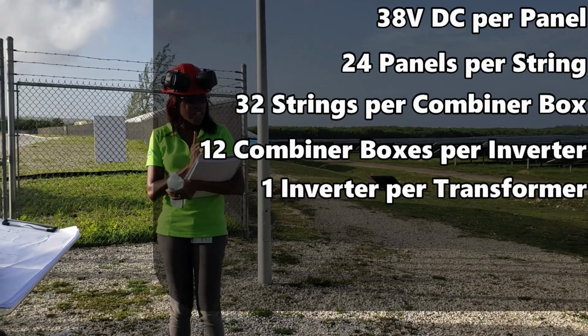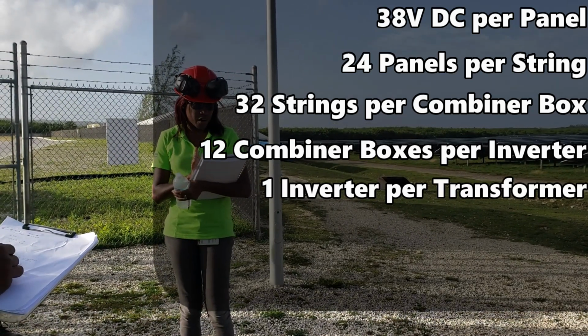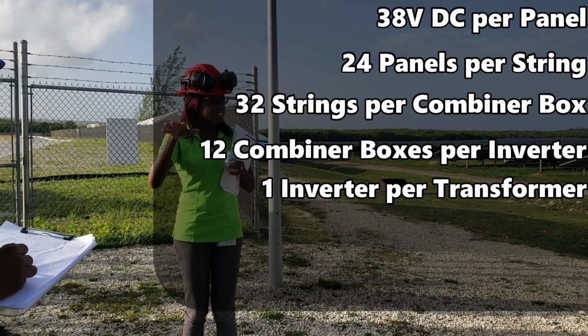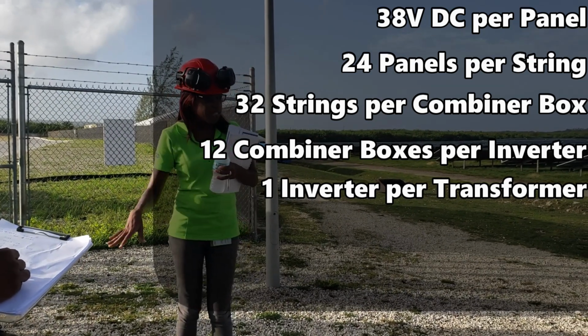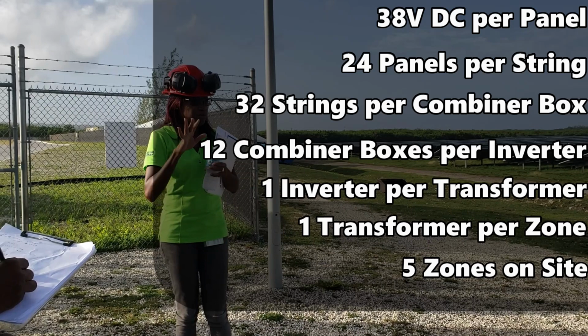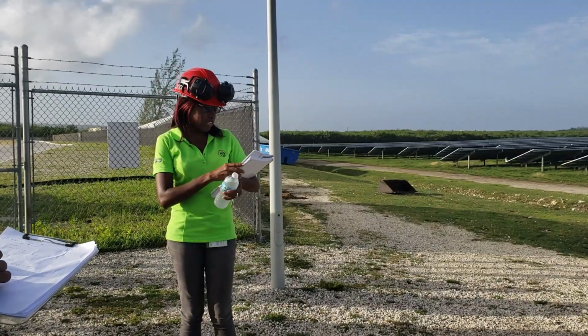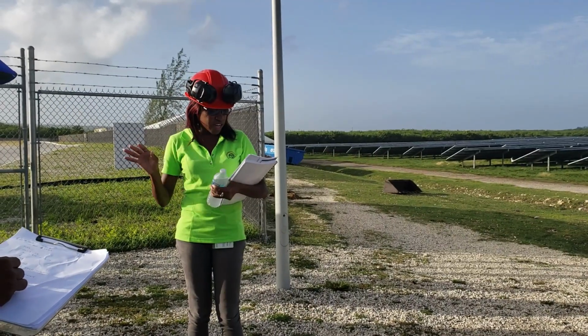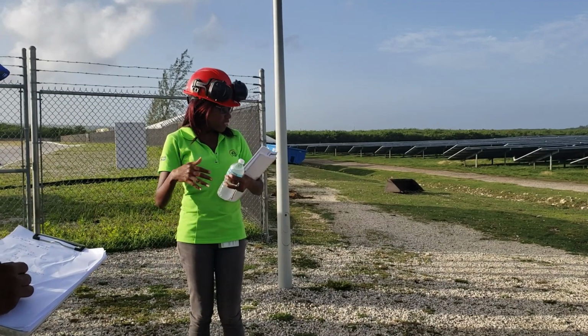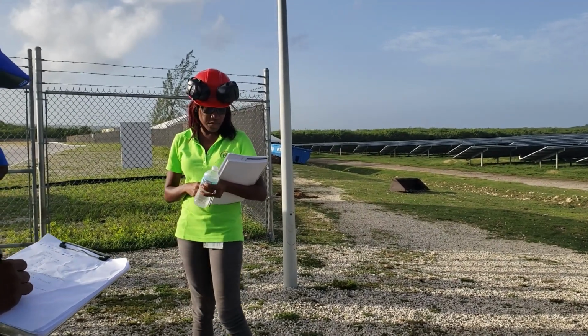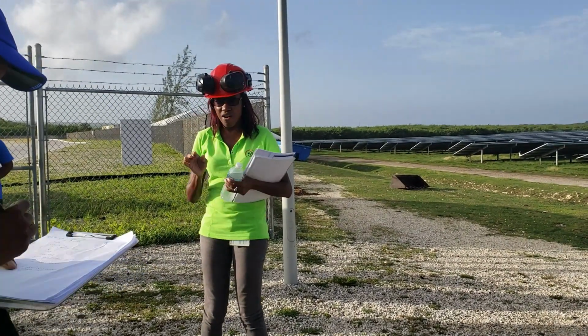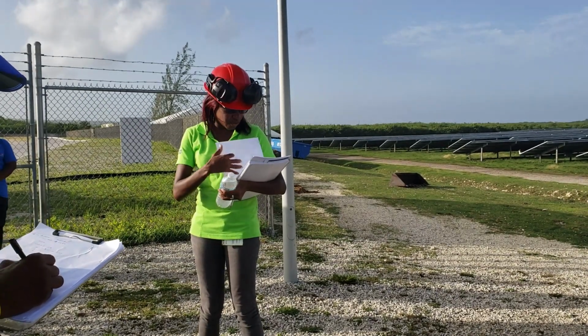Then you have one inverter per transformer. The site is separated into 5 zones, and each zone has a transformer, so there are 5 transformers on site. The output from the 5 transformers is combined and fed to the substation via underground cables. So on the technical side, that's where we are.